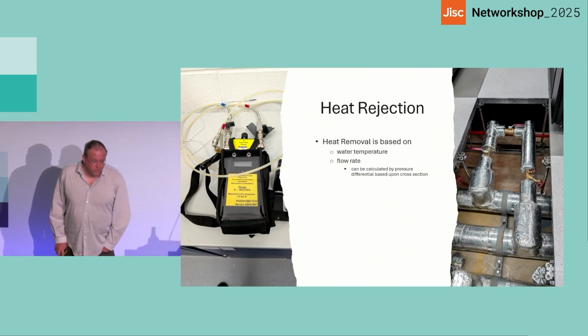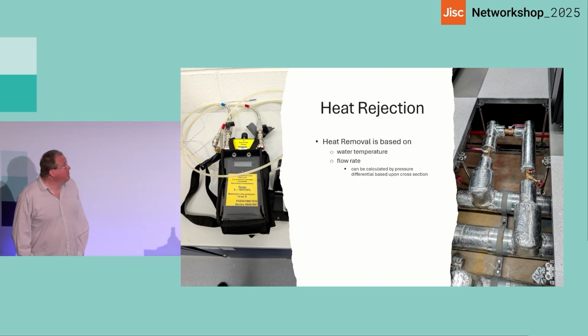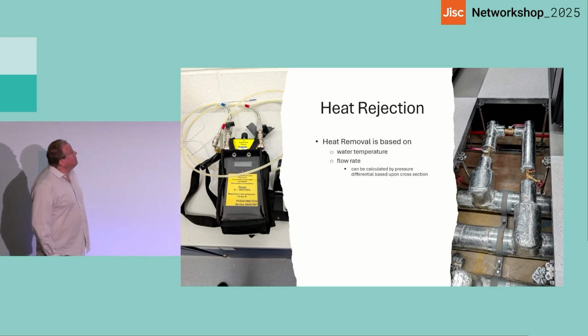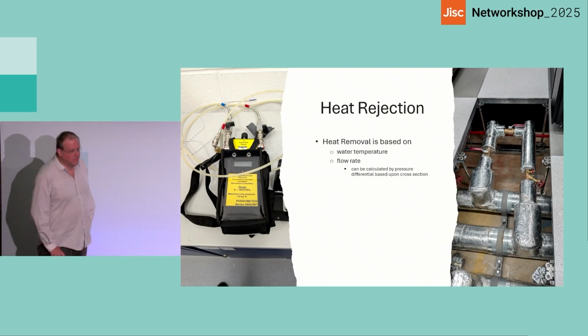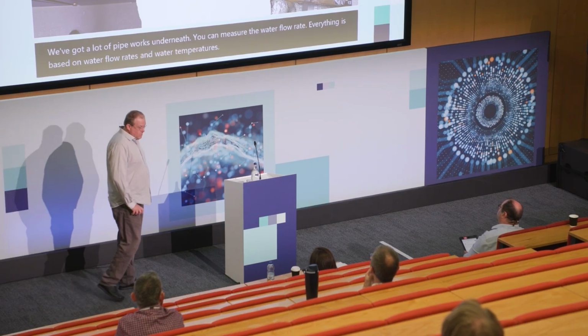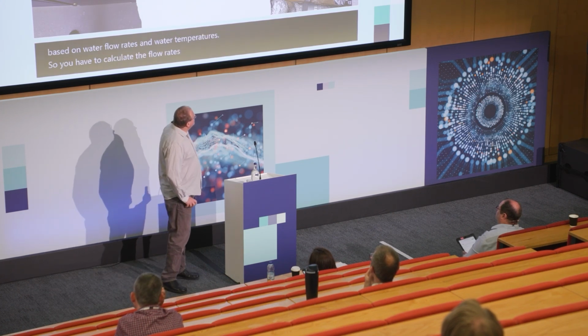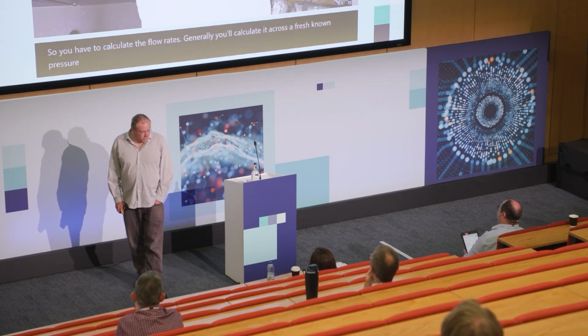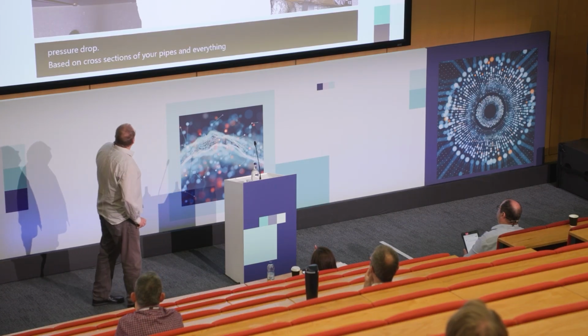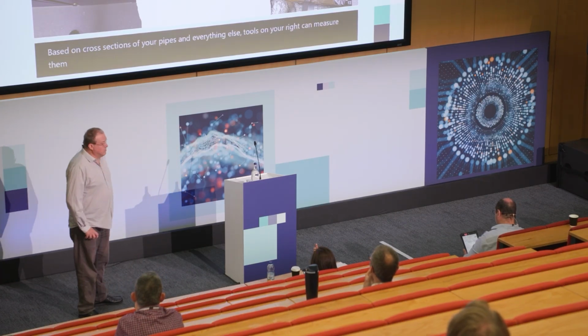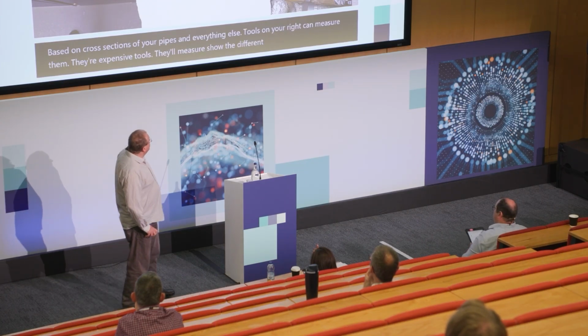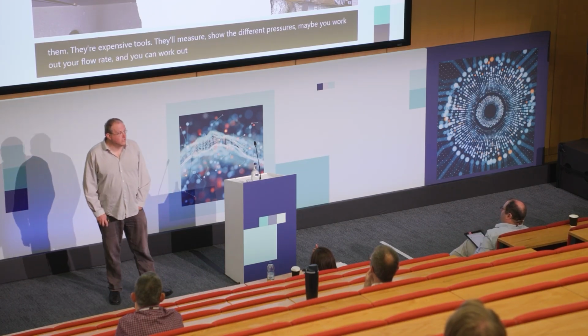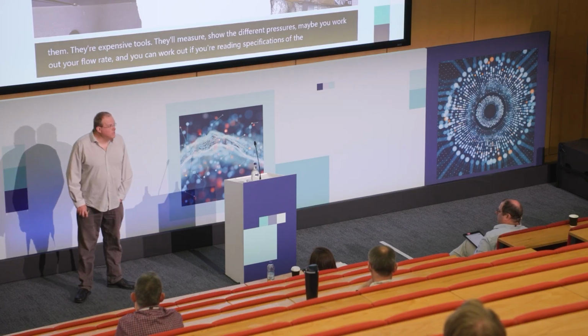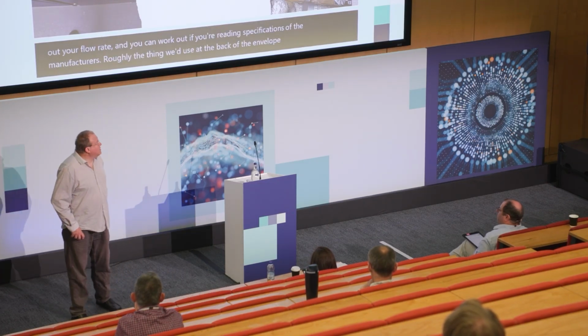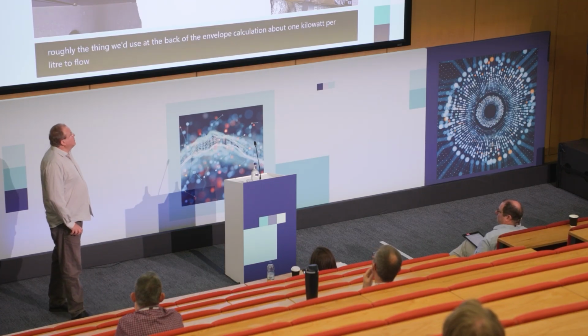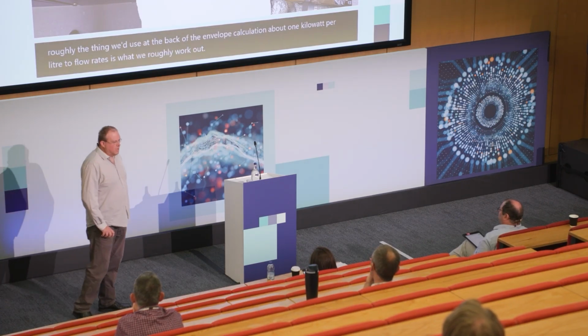As I say, we're talking about heat rejection. As I said, water has to flow through these tubes. We've got a lot of pipework underneath. You can measure the water flow rate. Everything is based on water flow rates and water temperatures. So you have to calculate the flow rates. Generally, you'll calculate it across a known pressure drop, based on cross sections of your pipes and everything else. The tools on your right can measure them. They're expensive little tools. They'll measure the different pressures. There you can work out your flow rate, and you can work out if you're within the manufacturer's specifications. Roughly, the back-of-the-envelope calculation we use is about 1 kilowatt per litre per minute of flow rate. It's a ballpark, a good start.